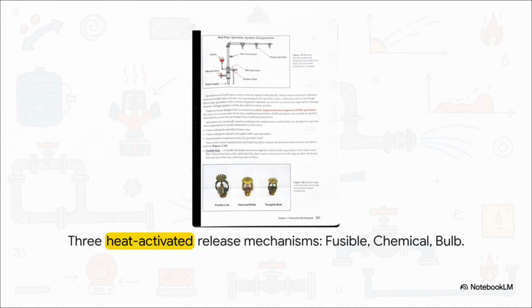So how do they actually trigger? What's genuinely fascinating about the 3 common heat-activated release mechanisms is the sheer mechanical genius of it all. There are absolutely no computer chips here. It is just pure physics. First, we have the fusible link. This holds 2 levers together that cap the water flow. When the heat from a fire reaches a specific temperature, the actual solder holding that link melts, the levers pop, and bam! Water flows.